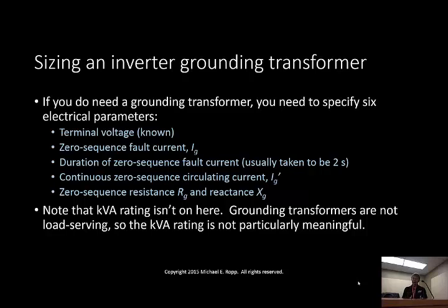What I'm going to show you now is a process by which you can size that thing so that, in theory, it should minimally impact your protection coordination. This is a procedure that we developed. It was published at the Western Protective Relay Conference, Schweitzer's conference out in Spokane. The background math is all in that paper.